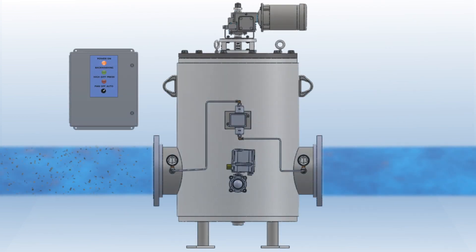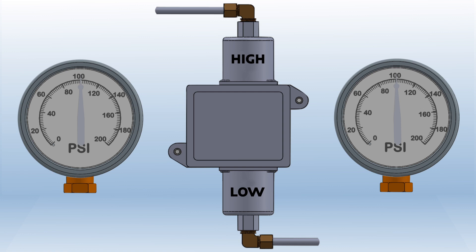If the eliminator sees a sudden high debris loading, the differential pressure switch can also trigger a backwash sequence. The differential pressure switch measures the difference in pressure between the inlet and outlet.